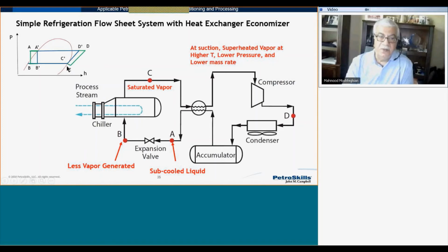On the pH diagram, the blue cycle is the original one without this heat exchanger, and the green one is with this heat exchanger. As you see here, originally the fraction of liquid was this much, but as a result of putting that exchanger and economizer in the middle, the fraction of liquid becomes from here to here. The fraction of liquid increases, the mass flow rate goes down, and the fraction of vapor is low.